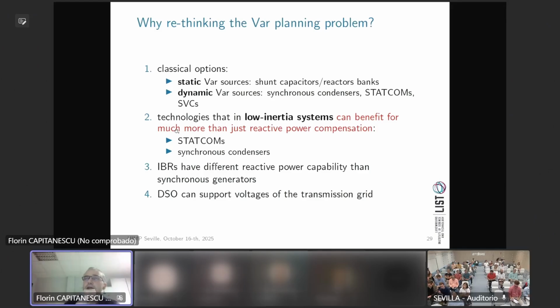Where the issues of reactive and active power join in the energy transition is that some devices, especially STATCOMs and synchronous condensers, contribute much more than just reactive power. In the past, synchronous condensers were the pariah of the power system, used just to control voltages. Now they provide inertia and contribute to short circuit current too. For me it's a silver bullet that needs to be exploited by operators. Some are already doing it - I think in Italy they buy and deploy them, Terna for instance. I think it's a very good idea.